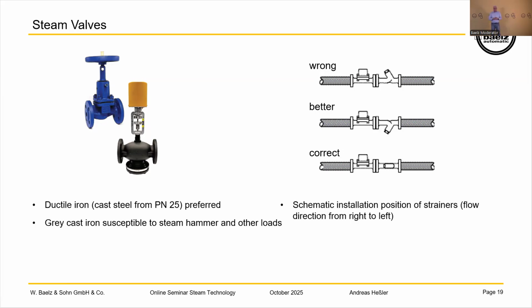On the right side, you see how we have to install a strainer in a steam pipe. The top one is very, very wrong, because in this one you will not strain the steam. The middle one would be better, but would normally be used when you have water. But if you want to do it very correctly, you mount the strainer horizontal to the steam pipe. If you're using the middle one and you have some condensate and some hammering of the steam, then the strainer can break. So it would be very good to use the lowest installation for the strainer.